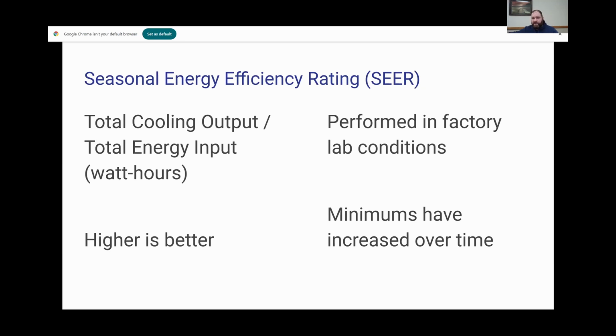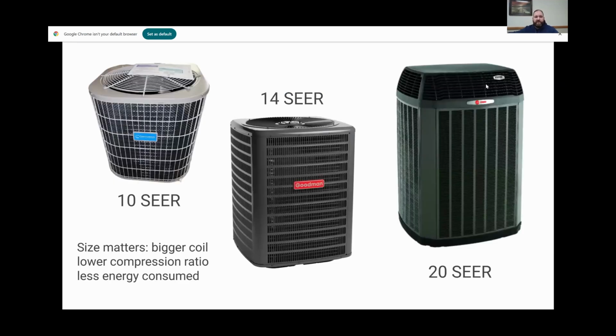It used to be that a 10 SEER was considered a pretty standard unit. Early 90s, that was a very common unit to see. Over time, those minimums have increased. I threw up just some generic pictures, not endorsing any of the brands here, but they were the best representations I could find. If you see a very small, older unit, a lot of them were like 2 foot by 2 foot by 2 foot, a little 2 foot cube, those are likely, on their best day, brand new from the factory, performing at about a 10 SEER rating.